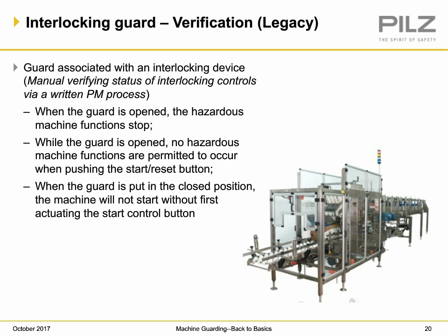And again, at the time, check for issues dealing with water, dealing with heat, dealing with vibration, because a lot of the legacy equipment is single channel. So anything could cause it to fail and possibly fail to the unsafe condition. And so I've shared this with customers, possibly putting this into their PM process. It could be daily, weekly. But here's the three-step process.